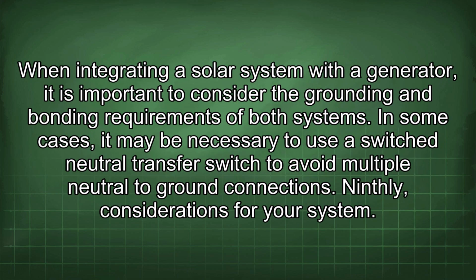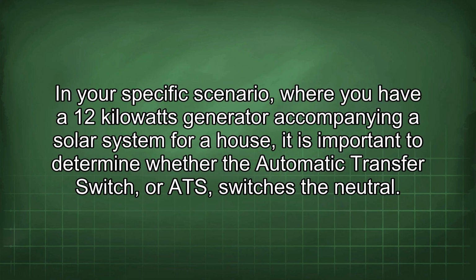When integrating a solar system with a generator, it is important to consider the grounding and bonding requirements of both systems. In some cases, it may be necessary to use a switched neutral transfer switch to avoid multiple neutral to ground connections. Ninthly, considerations for your system. In your specific scenario, where you have a 12 kilowatt generator accompanying a solar system for a house, it is important to determine whether the automatic transfer switch, or ATS, switches the neutral.